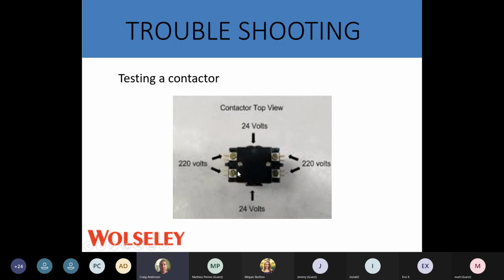I get calls on it every year. So always check your L1 to L2 when you're doing your 24 volts or your 220 volts to make sure you have power there. If you're going L1 to ground, L2 to ground, getting 110, and then you're going across L1 to L2 and you're getting 0, something is going on elsewhere. You're not getting your proper power to your outdoor unit.